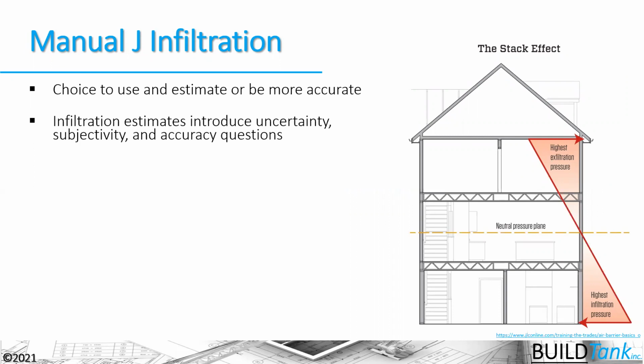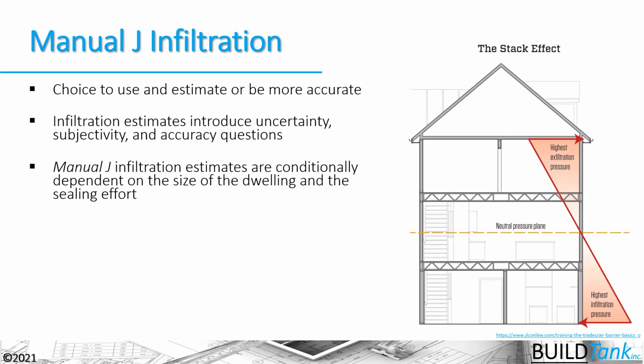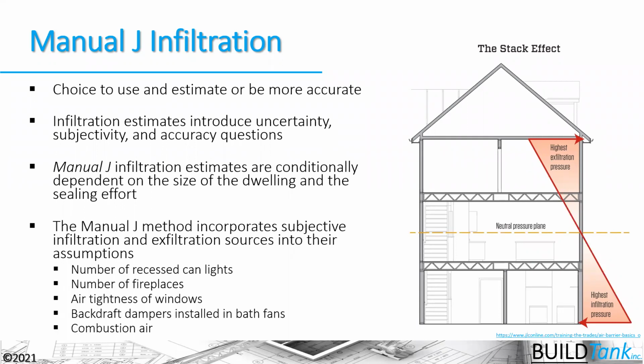The infiltration estimate process introduces a lot of uncertainty and subjectivity in the process of determining the air leakage of that home. It's based off of things like the size of the house and what they define as significant air sealing efforts in that house. Manual J will ask you to look at things like how many recessed cans are in the house, without really knowing whether they are airtight cans or non-airtight cans, how many fireplaces, and what the tightness of the windows in that house is. But you don't necessarily know those things.